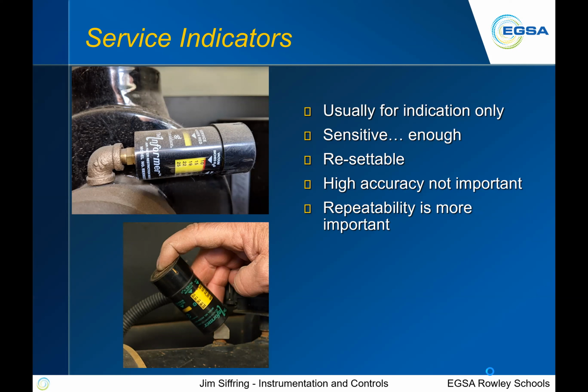So it's not terribly accurate, but you don't really need accuracy. It's mainly giving you an indication of when that air filter needs to be serviced. Repeatability is probably more important, so you don't end up clogging up a filter too far.